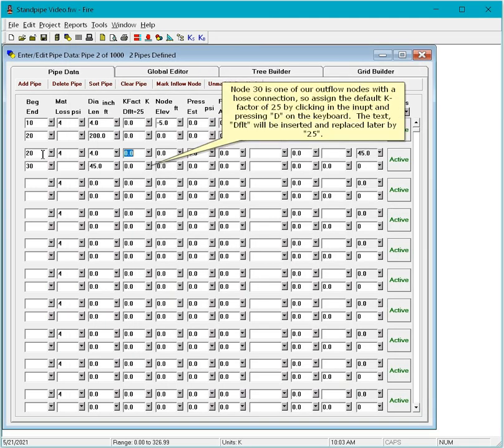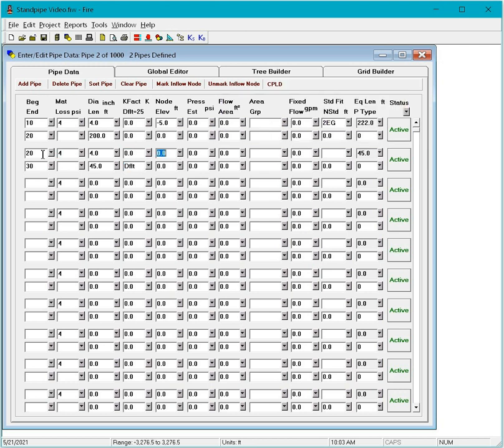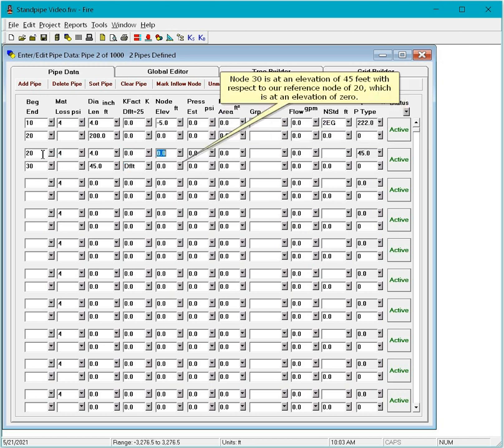Node 30 is one of our outflow nodes with a hose connection. So assign the default K factor of 25 by clicking in the input and pressing D on the keyboard. The text DFLT will be inserted and replaced later by 25. Node 30 is at an elevation of 45 feet with respect to our reference node of 20, which is at an elevation of 0.